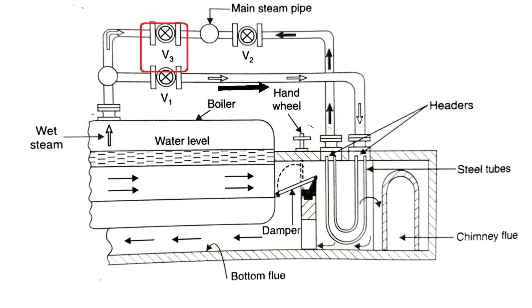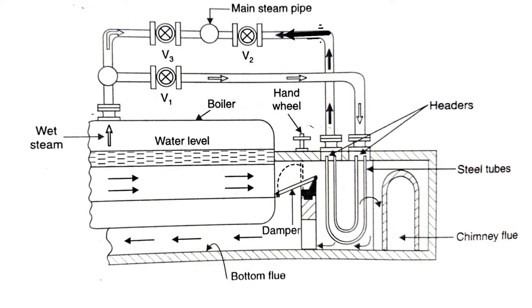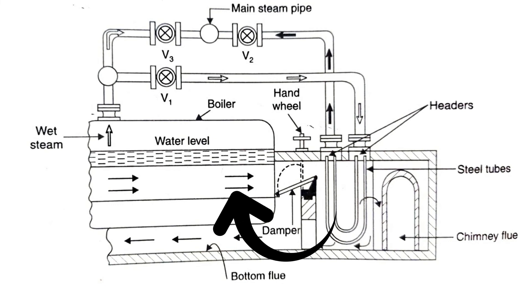When the superheater is in action, valve V3 is closed and valves V1 and V2 are open. At that time, the steam passes through the pipeline, then through the U-tube coil of the superheater, then through valve V2, and is supplied to the turbine. The path of the gases is controlled by a damper which is operated by a hand wheel.